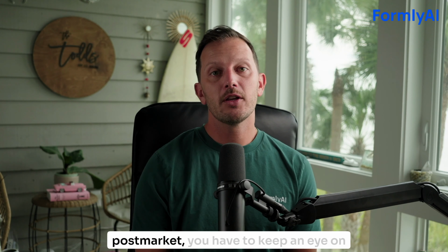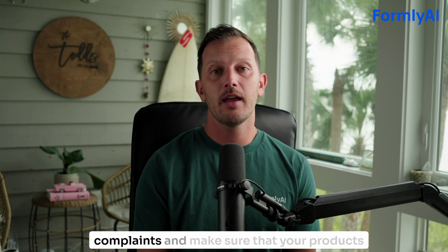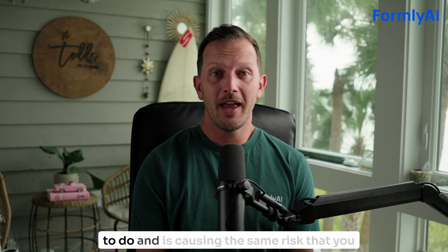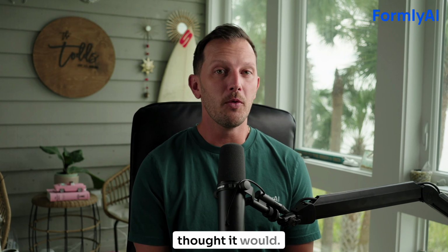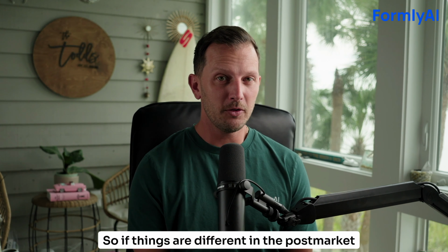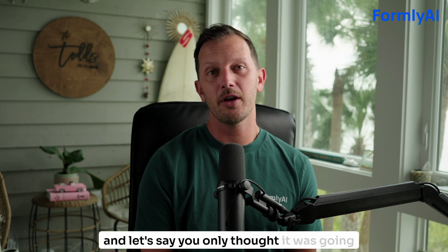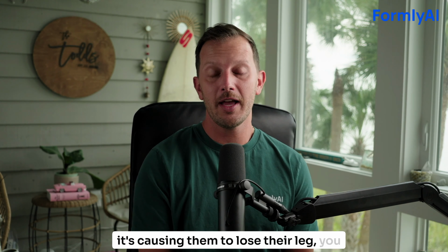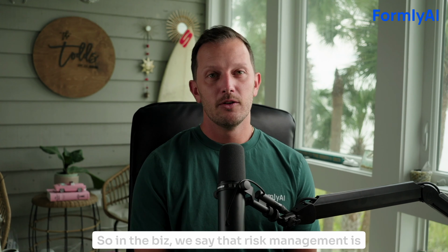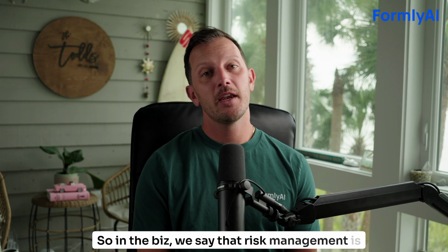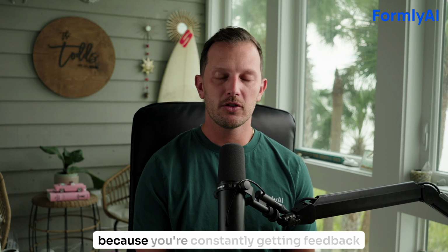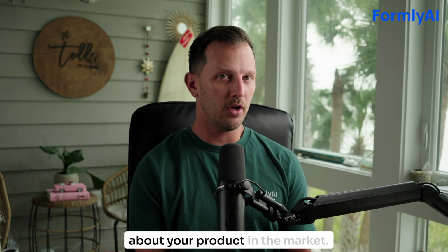Wrong. Post-market, you have to keep an eye on complaints and make sure that your product actually is doing what you said it was going to do and is causing the same risk that you thought it would. So if things are different in the post-market, and let's say you only thought it was going to be causing someone a minor scratch, and it's causing them to lose their leg, you might need to update your risk management. So in the biz, we say that risk management is alive. It's alive, it's alive! It's a live document, you're constantly updating it, and that's because you're constantly getting feedback about your product in the market.